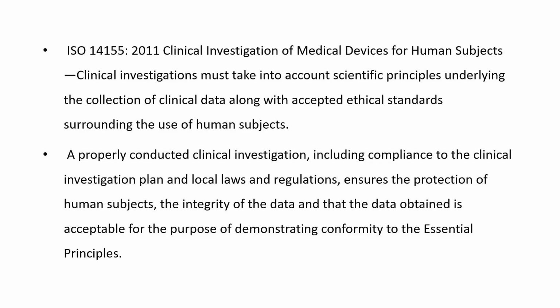A properly conducted clinical investigation, including compliance to the clinical investigation plan and local laws and regulations, ensures the protection of human subjects, the integrity of the data, and that the data obtained is acceptable for the purpose of demonstrating conformity to essential principles. So whatever data you get generated through these clinical trials has to conform with these realistic scientific principles.